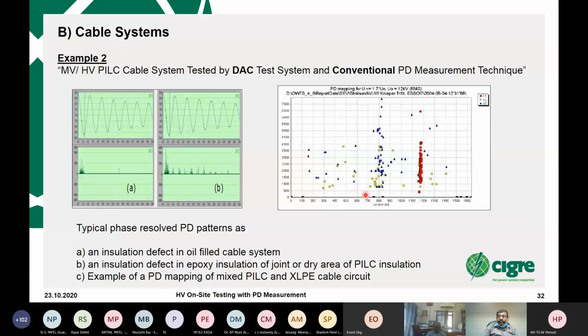And on the right-hand side, you see a cable, and what is shown here is the cable length. So this is 800 meters, and at one point, something like 100, on the cable, you see after each pulse, so these are the PD detected here, and several damped voltage wave shapes were applied. And so you can see, okay, what is here? And if you know the plan of the cable, as I said, you have to know what you are testing. Maybe there's a joint, then you know, okay, this is a fault in your cable joint, you have to look there. Or if nothing is there, maybe then the cable has something there, and you have to make a closer look at that point.